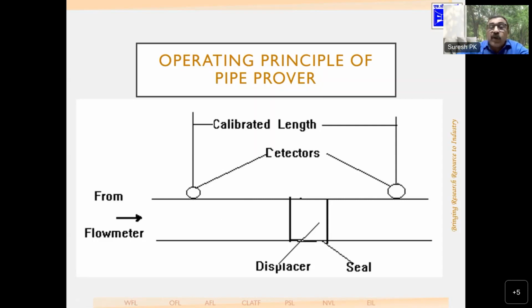Nowadays they generally use optical detectors, which touch neither the fluid nor the displacer. They find out whether the displacer has passed the detector. At the point of passing the detector, the volume is known. So between these detectors, what is indicated by the meter is found out. That is how you find the total volume passed through the meter at what flow rate. How much time it takes for the displacer to move from this place to this place is also known. So if this is a 100 liter volume and it takes 10 seconds, then the fluid is moving at 10 liter per second.